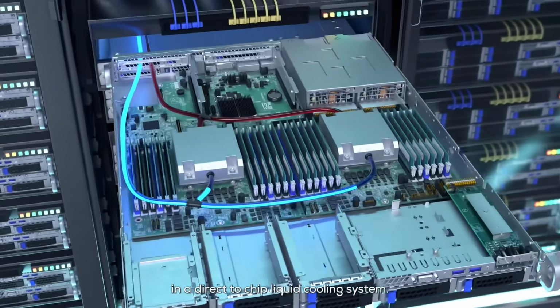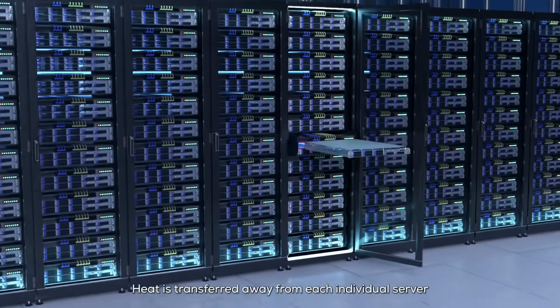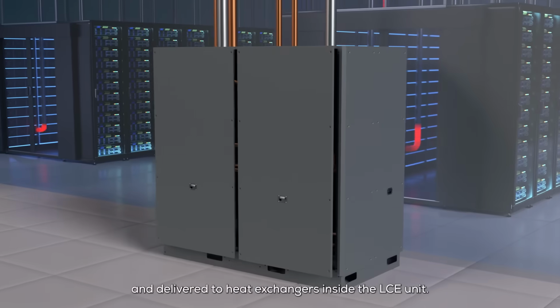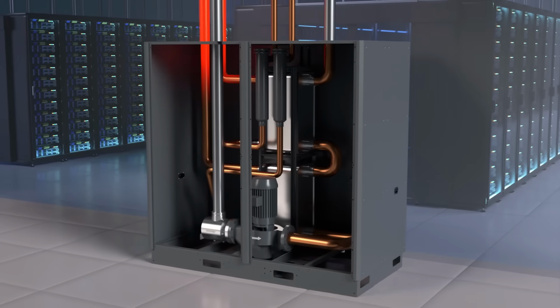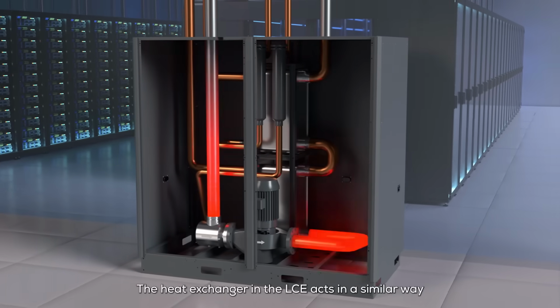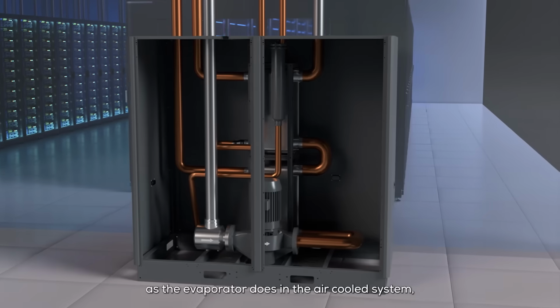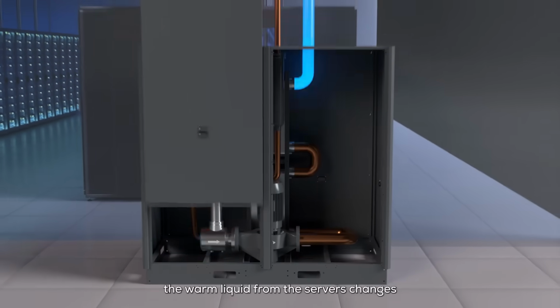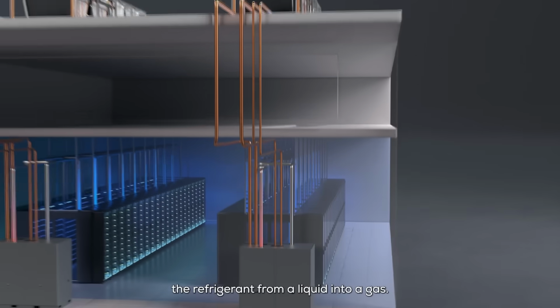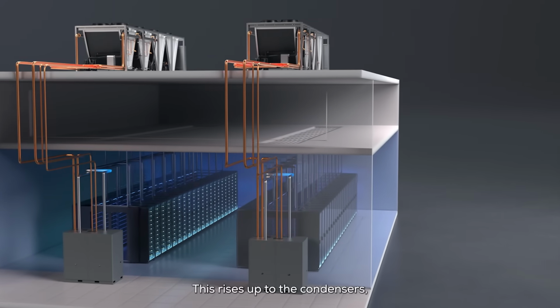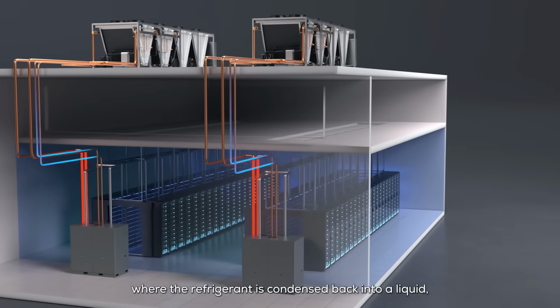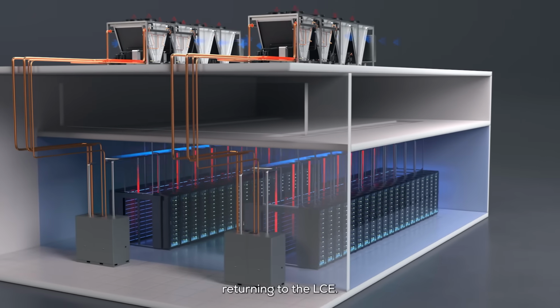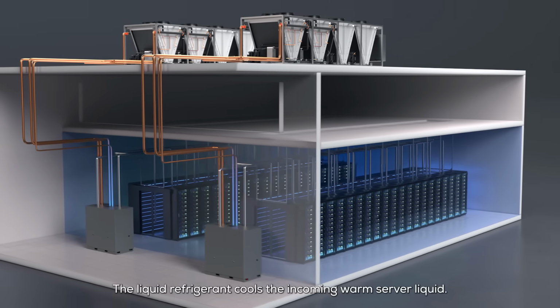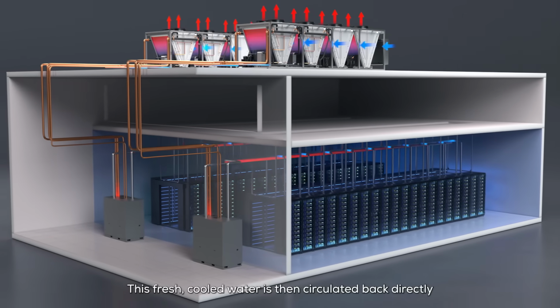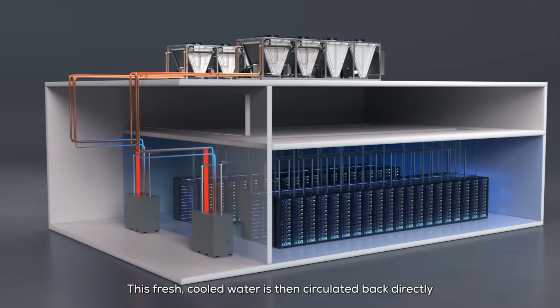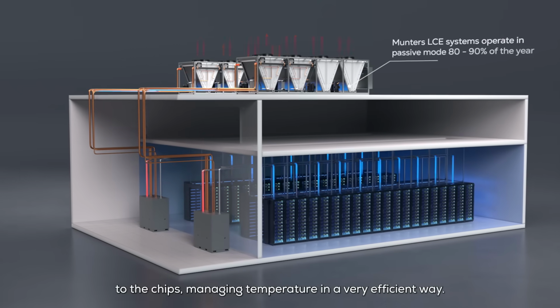In a direct-to-chip liquid cooling system, heat is transferred away from each individual server and delivered to heat exchangers inside the LCE unit. The heat exchanger in the LCE acts in a similar way as the evaporator does in the air-cooled system. But instead of warm air, the warm liquid from the servers changes the refrigerant from a liquid into a gas. This rises up to the condensers, where the refrigerant is condensed back into a liquid, returning to the LCE. The liquid refrigerant cools the incoming warm server liquid. This fresh cooled water is then circulated back directly to the chips, managing temperature in a very efficient way.